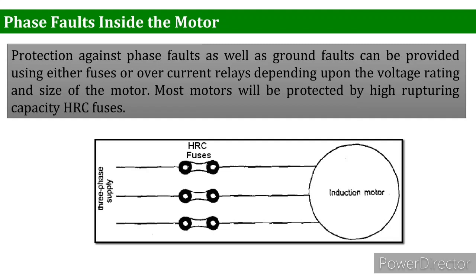So the fusing current should be greater than the starting current of the motor. The fuse operating time should be less than the permissible locked rotor time of the motor. The locked rotor time is the time for which the motor can be safely stalled with full supply voltage applied to the stator.